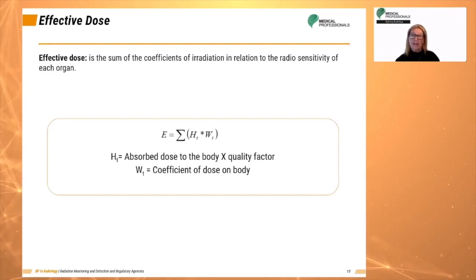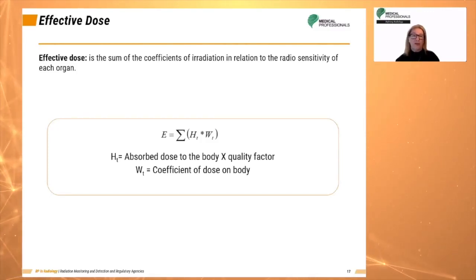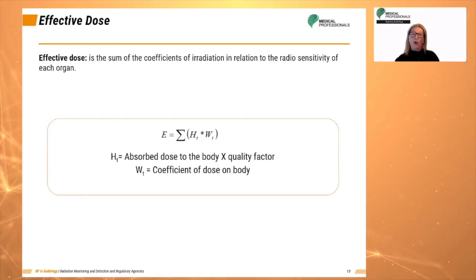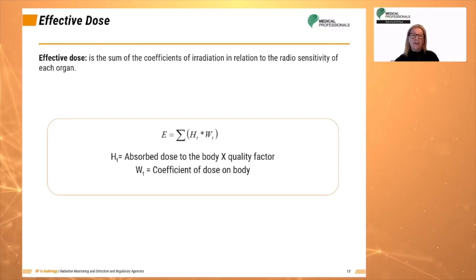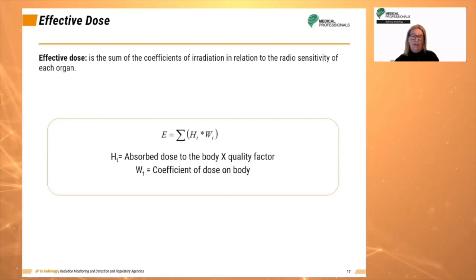Effective dose is not intended to apply to a specific patient; the actual risk might be higher or lower depending on the size of the patient and the type of procedure. The effective dose reflects non-uniform radiation absorption of partial body exposures relative to a whole-body radiation dose and allows comparisons of risk among different CT examination protocols. The SI unit is the sievert or millisievert; the conventional unit is the rem or millirem.